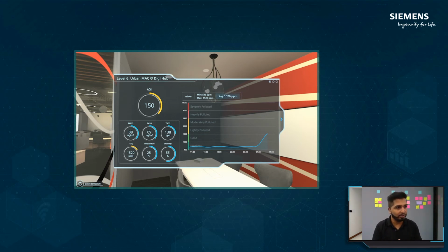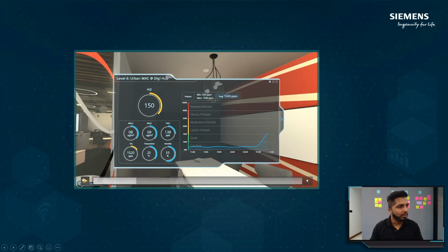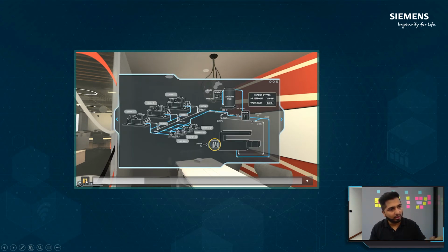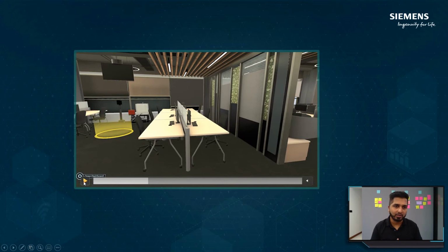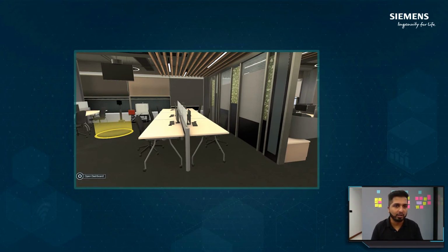So what we did here was we tried to learn as we collect the data, and with maintenance logs and everything, a knowledge graph, we can actually advise the engineer that this could be the issue. In this case, it's telling that this outlet valve was not maintained for the past 3 months, so the carbon dioxide is not able to go outside, and this is the reason behind the CO2 being higher. So it is a guidance. It is not the truth, but it is guidance that it could be a fact. Maybe you should have a look at it. It gives a priority of things for him to look at, so this way he can easily fix it.